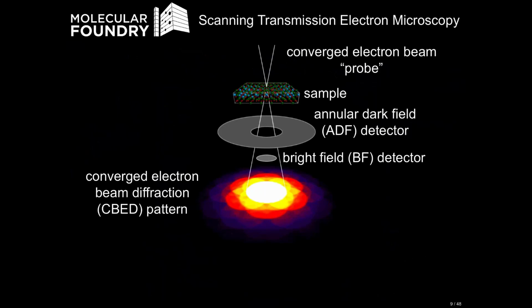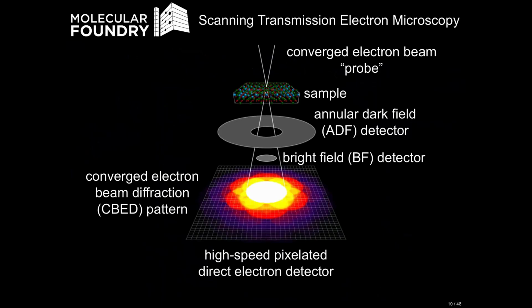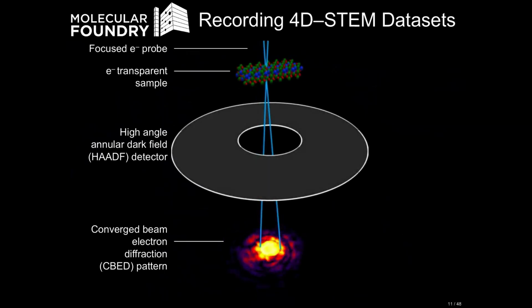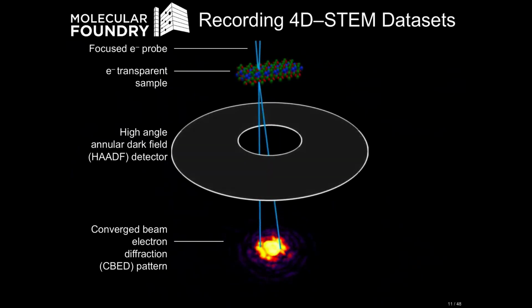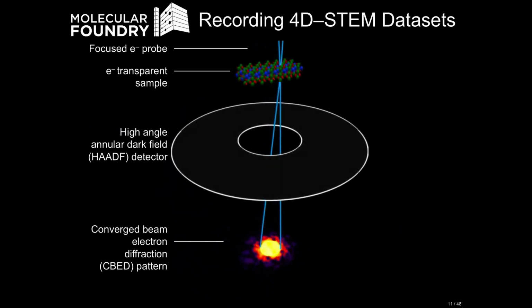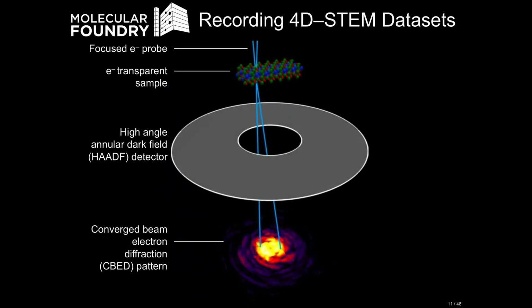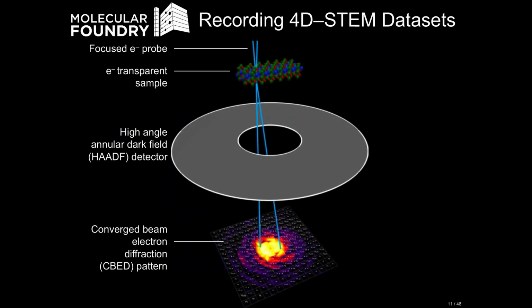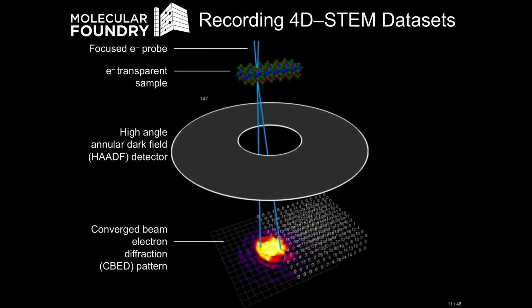That used to be the only possible experimental geometry for imaging. The recent introduction of direct electron detectors means they run at high enough speeds that if we place one in the far field, we can record every single pixel of the diffraction pattern under each STEM probe. If I play this movie showing what it looks like, as you scan your beam across the sample using the STEM scan coils, you get a scattered signal on your high-angle annular dark field detector, but you can also use the high-speed direct electron detector to record the full pattern.